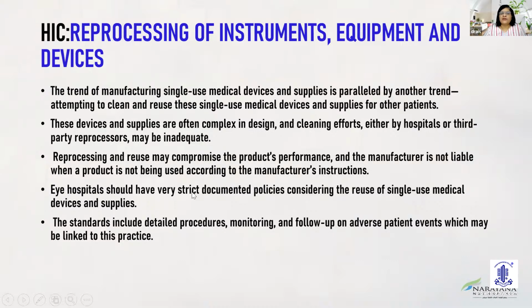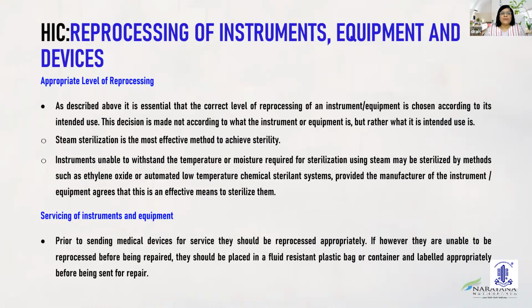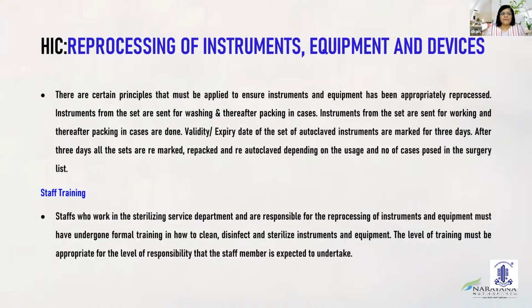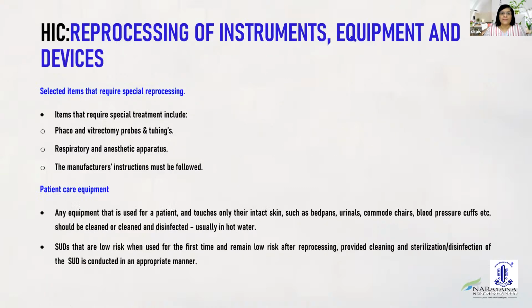Eye hospitals should have a strict documented policy considering the reuse of single-use medical devices, and they should have detailed procedures and follow-ups. Appropriate level of reprocessing should be done. Servicing of instruments and equipment should be done. The staff who work in the sterilizing service department and are responsible for reprocessing of instruments and equipment must have undergone formal training in how to clean, disinfect and sterilize instruments and equipment. The level of training must be appropriate for the level of responsibility that the staff member is expected to undertake.